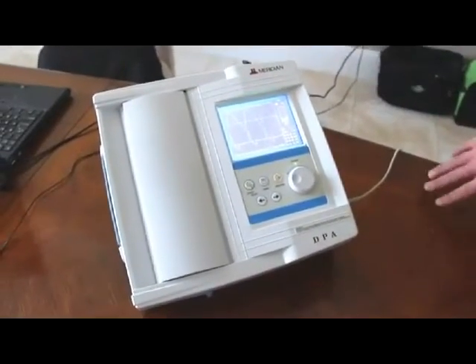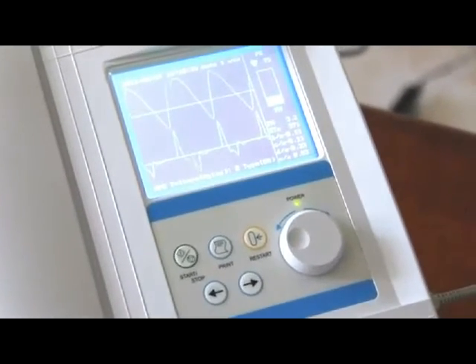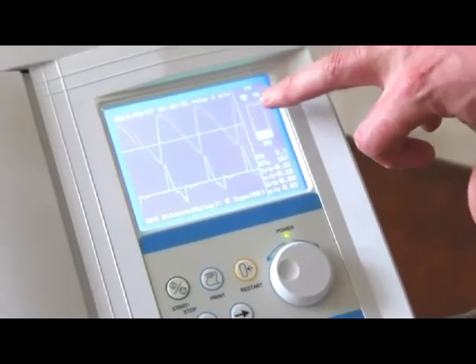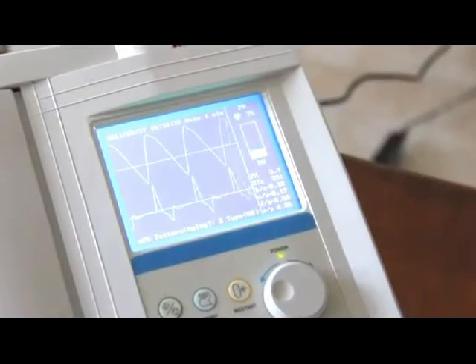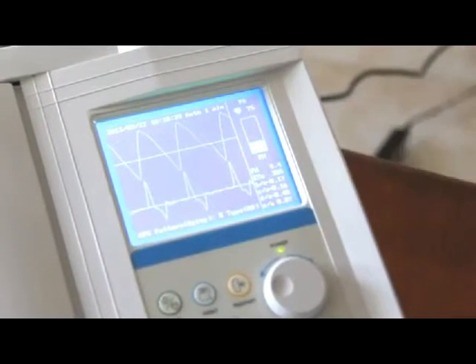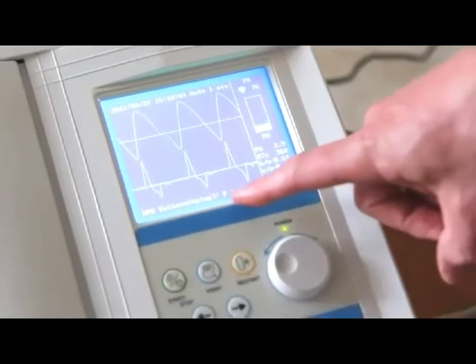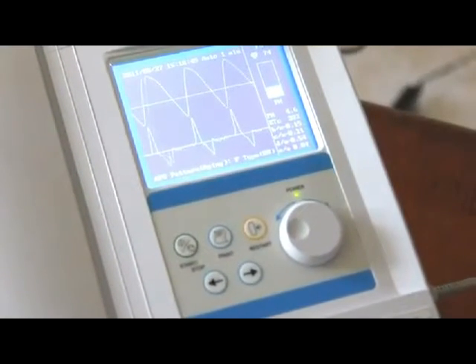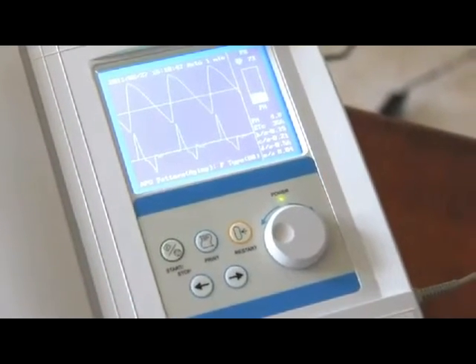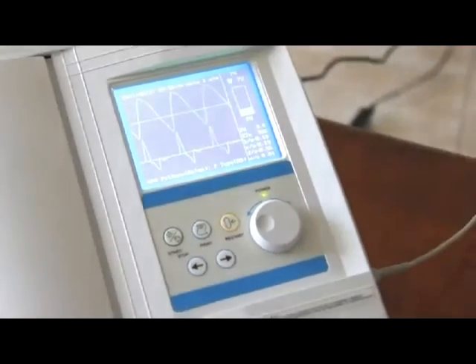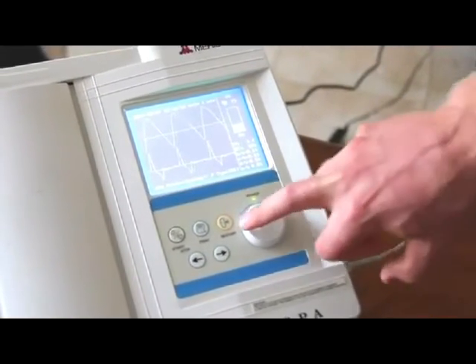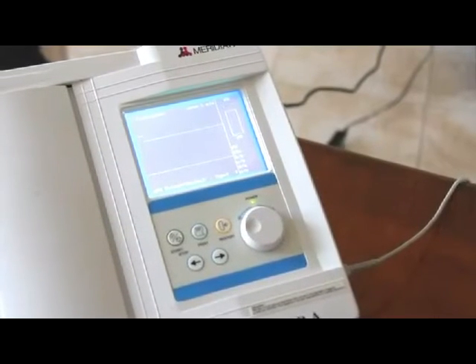Once we have the clip on there, then we look at the blue screen and make sure that all our parameters are up and running, which the heart will be beating, that will show the pulse rate, will show the hydration levels here, as well as we have the grade and the number. So we know that we got everything established, then we can hit the reset button, and that starts the test.